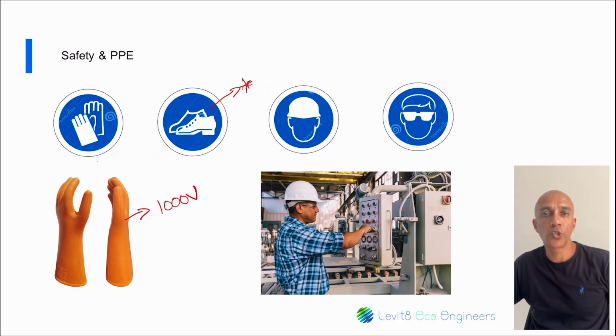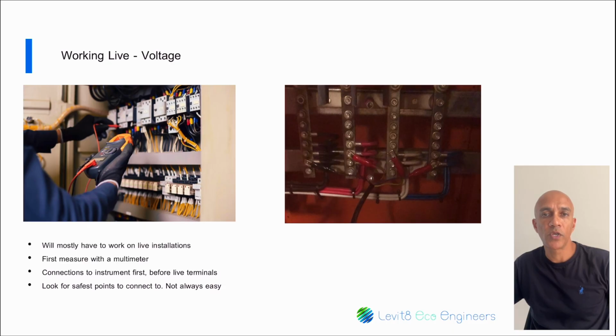If that is the case, make sure that you first measure the live points with a multimeter to ensure that there is in fact voltage on those points. And after you switch off, then you can check the connection again and make sure that there is no voltage. Check it with your multimeter before you start doing the connections. Now make sure that you connect your voltage and current leads securely to your instrument first and foremost, and not after you have connected them to the live parts, that is the circuit breakers or your terminals in your panel. You will very likely end up getting an electrical shock if you do it the other way around. So it's always instrument first and then onto the live terminals.